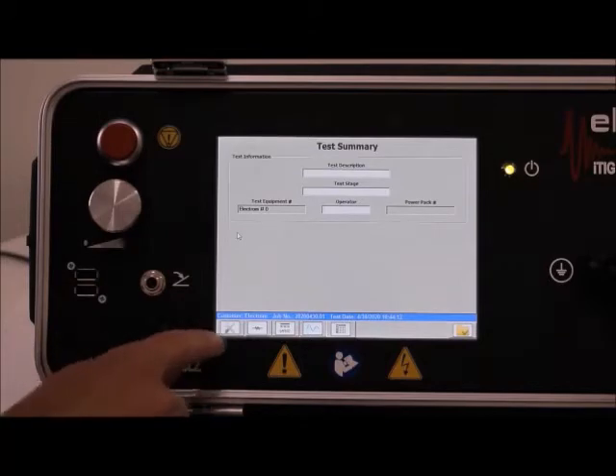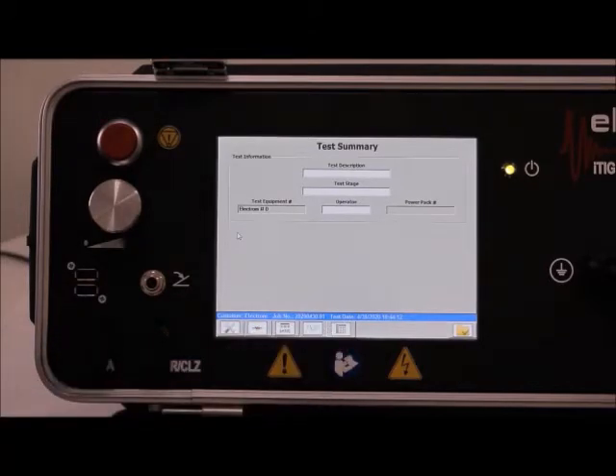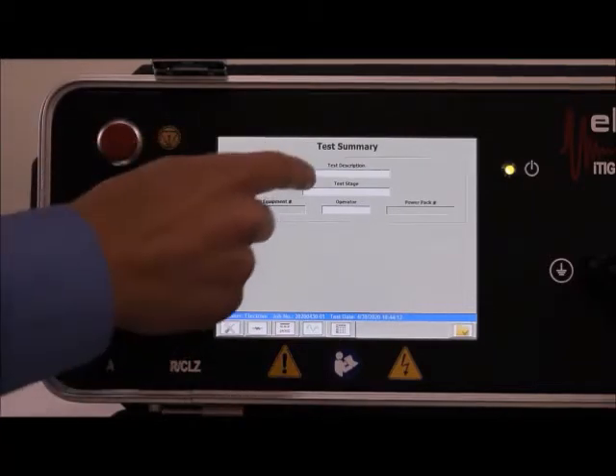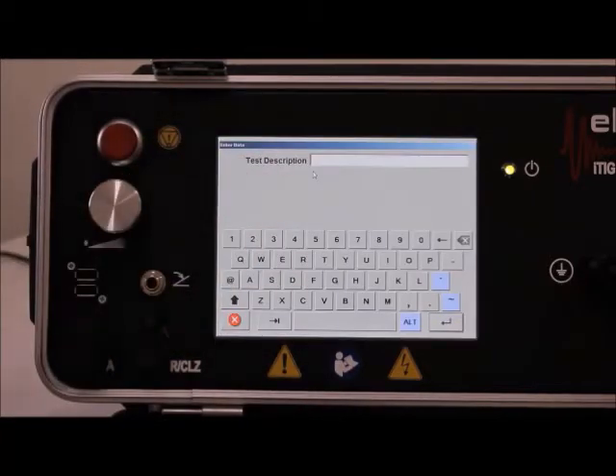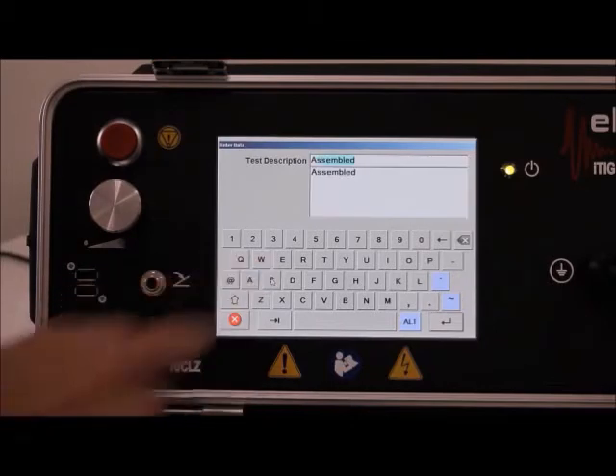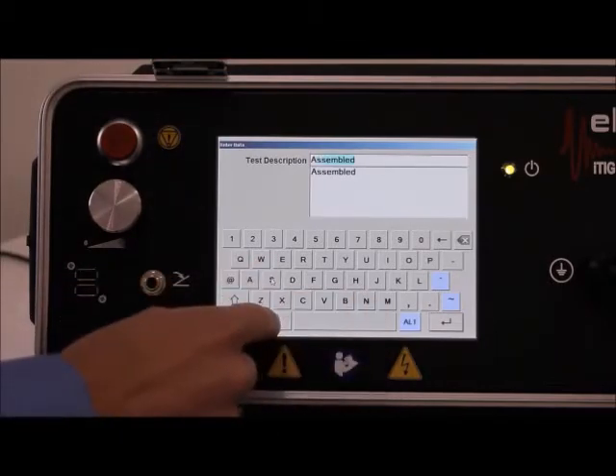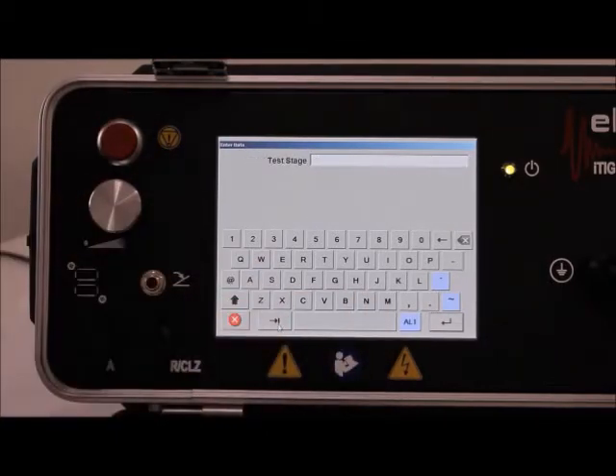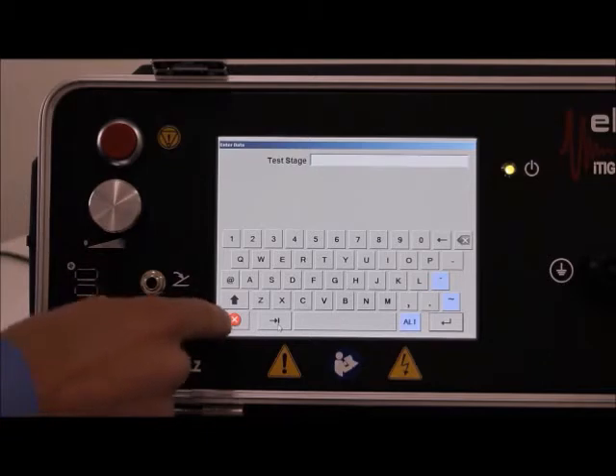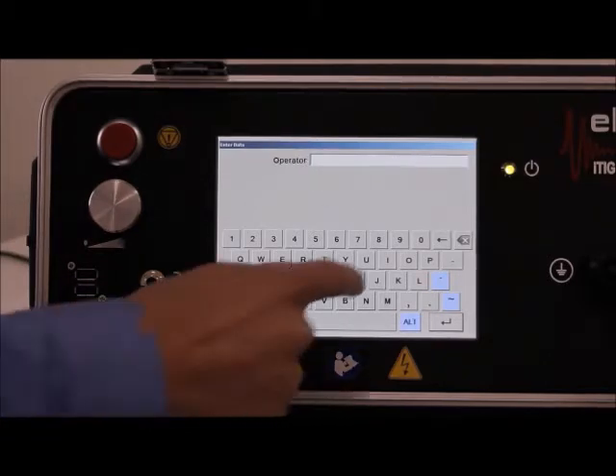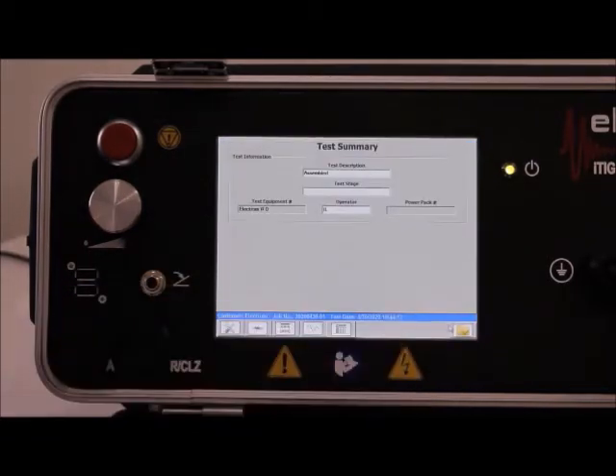We will move from left to right along the tabs in the bottom row here. We're actually on the last tab, the test summary screen. We can enter in a test description. I like to add some information about what we're testing on. In this case, it's an assembled motor. You can use the tab button here to scroll down the list. We can add a test stage if it's an incoming motor or freshly rewound outgoing motor, for example. I'll leave that blank for now. Operator information, I like to use my initials.